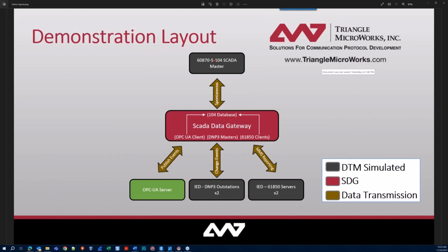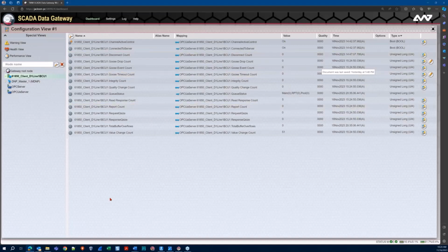So, of course, what this looks like for you will vary depending on what devices you have and what protocols you're using. But today I chose to use 60870-5-104, a pretty common SCADA protocol, at least in certain parts of the world. I'll be providing that data that I aggregate all together and then passing it back up. So I went ahead and did a little bit of the configuration ahead of time. I've brought in one 61850 client, as well as one DNP3 master, but now we're going to be creating the rest of what we saw in that last diagram.